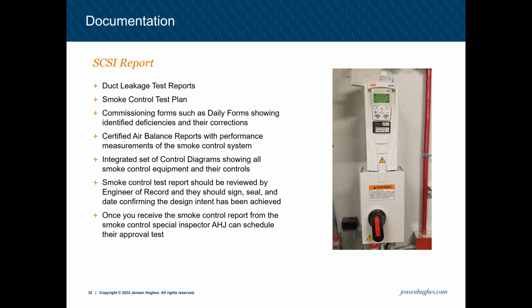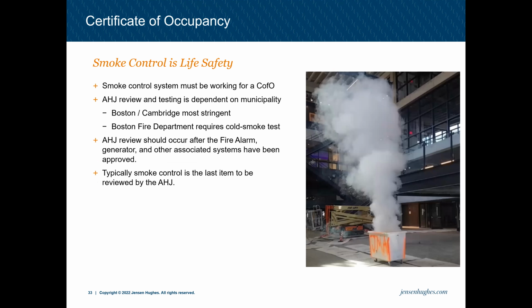The smoke control special inspection report at the end is required to be signed and sealed by the engineer of record, to ensure that the testing is correct and the system does function as required by the building design and the engineer of record's design for the smoke control system. Usually, once you receive that smoke control report from a special inspector, the AHJ will then schedule their approval test. The approval test does vary by municipality. Again, usually Boston and Cambridge are the most stringent. Other municipalities vary a little bit based on their experience with the types of systems.